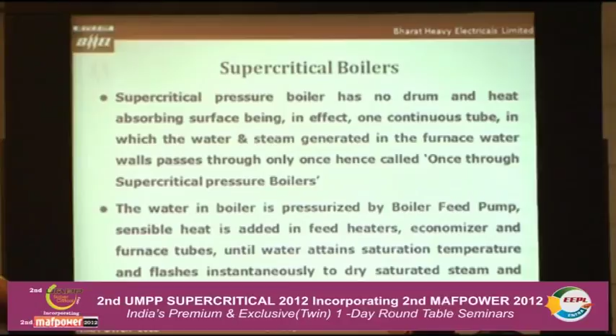Whatever water comes in has to go to the superheater. If any amount of debris comes in, it is going to damage your turbine blades. So the water treatment plant has to be ultra clean. Okay, that is a minus. The other thing is the entire pressure is built by the boiler feed pump. In fact, the boiler feed pump has to take care of the additional pressure that has to develop to force the entire water through the water wall circulation, maybe around 40 kg more than with the conventional 500 megawatt boilers.